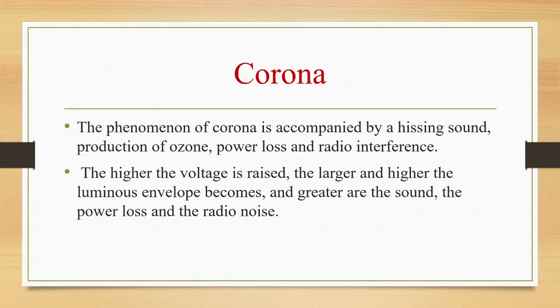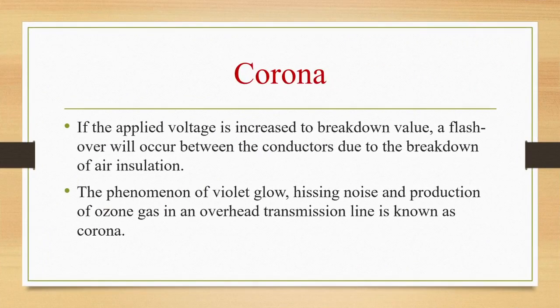The phenomenon of corona is accompanied by a hissing sound, production of ozone, power loss and radio interference. The higher the voltage is raised, the larger the luminous envelope becomes, and the greater are the sound, the power loss and the radio noise. If the applied voltage is increased to the breakdown value, flashover will occur between the conductors due to the breakdown of air insulation. The phenomenon of violet glow, hissing noise and production of ozone gas in an overhead transmission line is called corona.